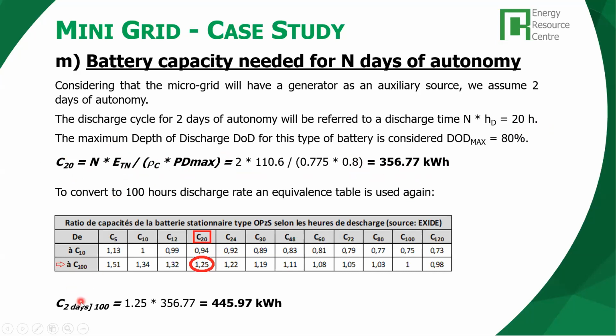If we want to have the capacity C100, we go to the manufacturer, we see what the conversion factors are to change C20 to C100. We need to multiply by 1.25. So we do that, and our same battery, 2 days of autonomy, with a capacity of 100 hours of discharge, would be equivalent to 446 kilowatt hour.